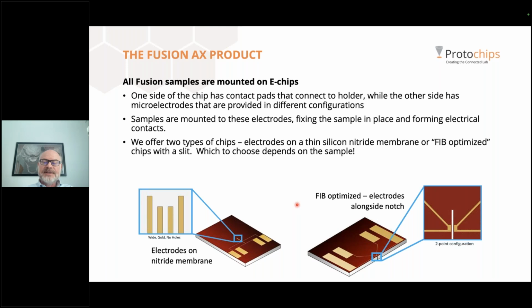Now, I mentioned the E-chips. As Zayna said, all fusion samples are mounted on E-chips. E-chips are a small silicon die. One side of the chip has contact pads, like here and here, and these serve as an interface with the probes on the holder. The other side has microelectrodes that terminate either on a membrane or near a notch in the die. Samples are placed on or near these microelectrodes, then they're attached physically and electrically, forming a circuit.